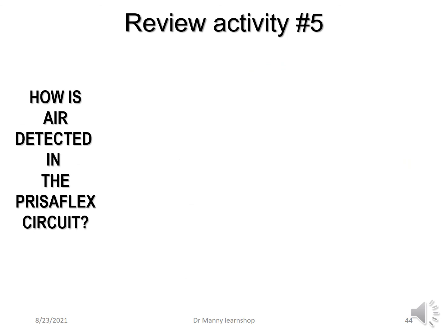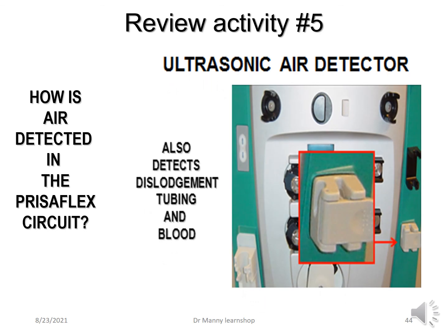Review activity 5. How is air detected in the Prismaflex circuit? Well, air is detected with the use of an ultrasonic air detector, which is located in the return line. And it also detects dislodged tubing and blood. But it's in the return line before blood goes back to the patient to avoid air embolism.